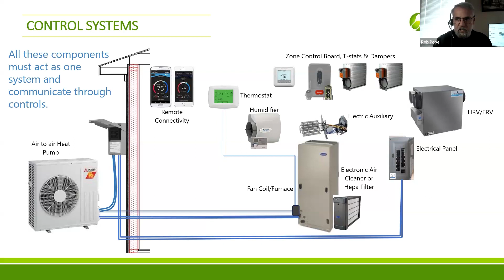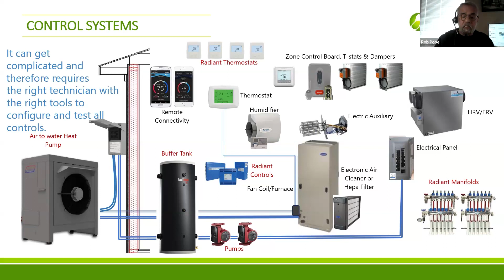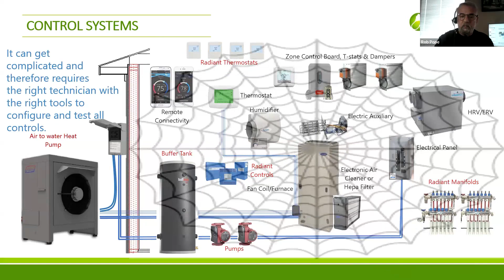Now, if we add a radiant system, as you can see, it starts to get pretty crowded in the control room there. Now we're going air to water heat pump, probably. We're adding a buffer tank, some pumps, some radiant manifolds, more radiant thermostats, radiant controls, and so on. As you can see, it can get complicated. So just the controls alone, making sure all the wiring is done to all the components properly, and each one of those components is configured to talk to each other. They have to have a handshake with each other, and they have to know each other exists. There's a little more to it than most people realize. It's a web.